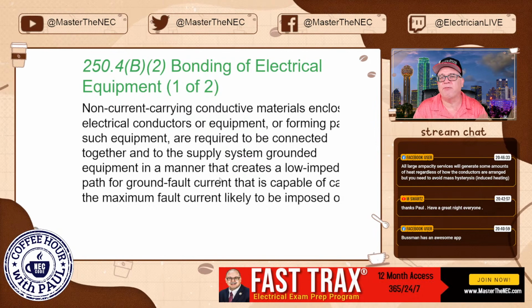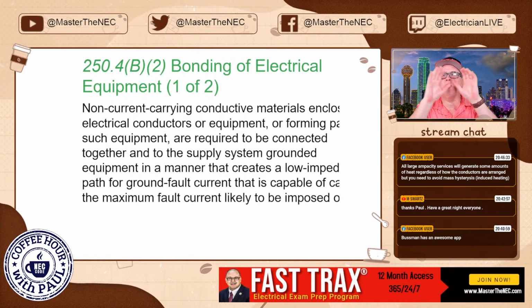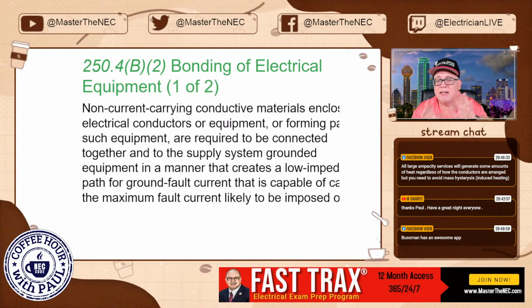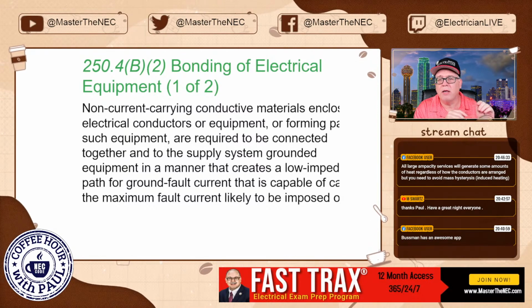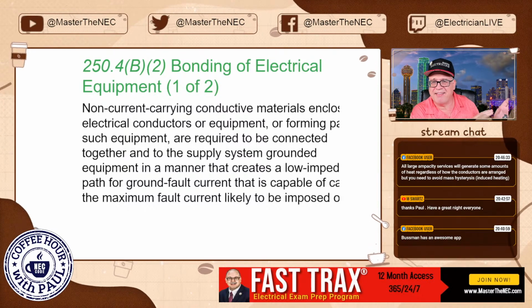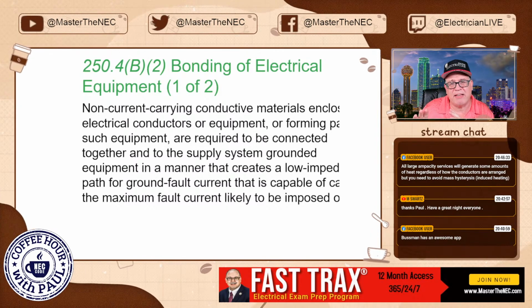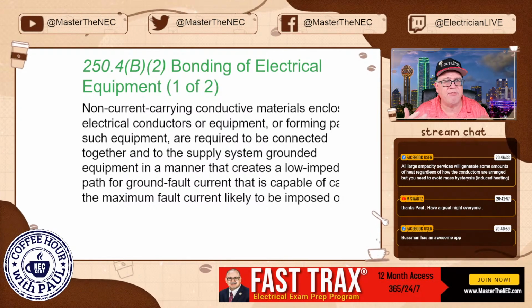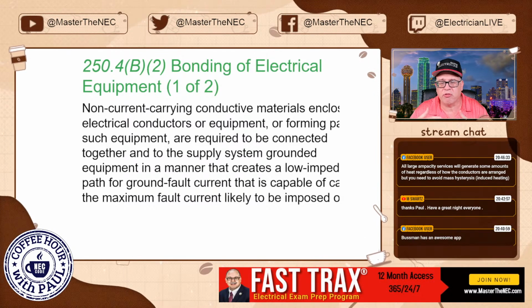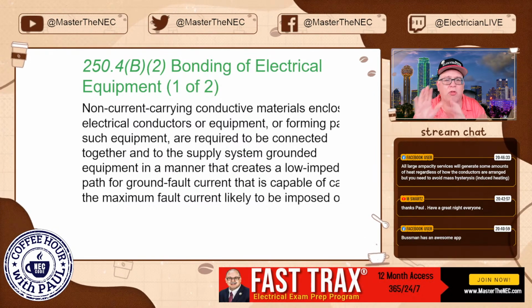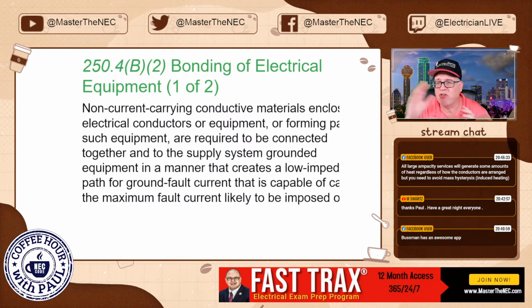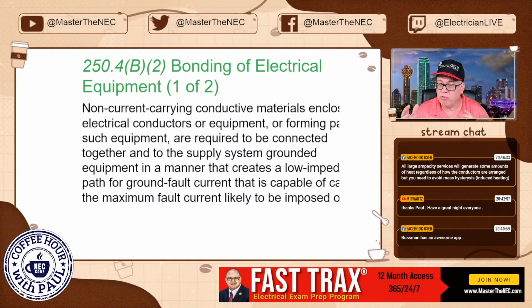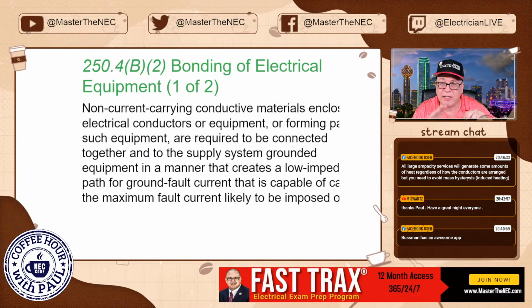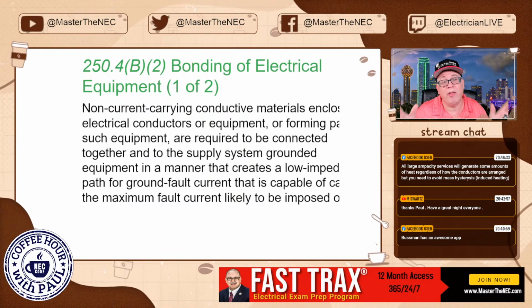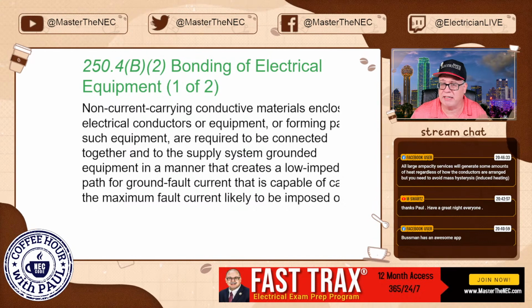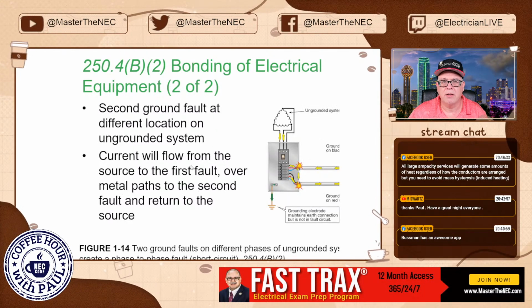Trying to understand the difference between a grounded system and an ungrounded system, remove the complexity of having a grounded conductor or a connection to earth. We're just saying get past that. Now we're going downstream of that source. We're still going to have to use raceways and make sure those couplings are done right, those lock nuts are done right, we make all those connections properly. We still got to do all that. So if you remove all of that about the grounded conductor and the connection, doesn't it sound very similar to what you would do on a grounded system? Sure it does.